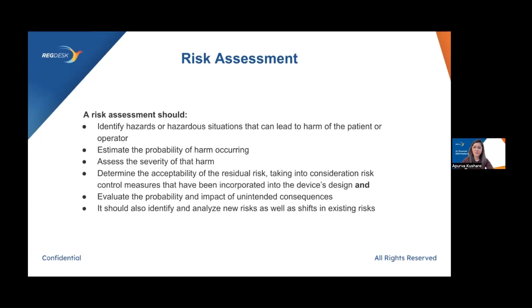This slide, I feel, is very, very important to consider. A risk assessment should be able to identify any hazards or hazardous situations that can lead to harm to the patients or the operators. It should also be able to estimate the probability and severity of the harm, and determine the acceptability of the residual risks, taking into consideration the risk control measures that have been incorporated into the device design. It should also evaluate the probability and impact of unintended consequences. Your risk assessment should also identify and analyze any new risks as well as any shifts in the existing risks. This is one of the important tools that manufacturers can use in order to make a determination whether your change is significant or not.